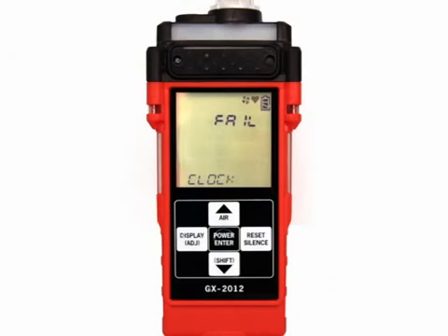If a clock failure alarm occurs, the internal unit date has been changed to something unreasonable like month 15 or day 34. Press and release the Reset Silence button to continue into normal operation. There will be no data logging function if you operate the instrument after a clock failure. Attempt to change the date using the Date Time menu in maintenance mode. If the date cannot be set correctly, contact RKI Instruments as soon as possible.